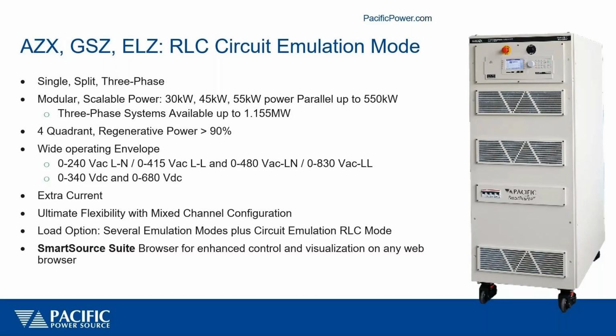It has a wide operating environment for voltage and frequency, so you can program up to 480 volts line to neutral or 830 volts line to line, so you can handle 600 volt grids as well as 480 volts and 400. And for DC applications, it has three outputs up to 680 volts DC each. So it allows you to do both AC and DC type testing.